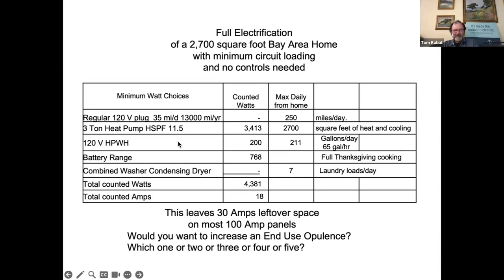And then the 120 volt water heater can deliver 211 gallons of hot water per day, about 65 gallons in hot water rush hour. So you can increase that by just picking a bigger tank size. Pick an 80 gallon tank and you can get about 80 or more gallons of hot water out of it with a mixing valve.